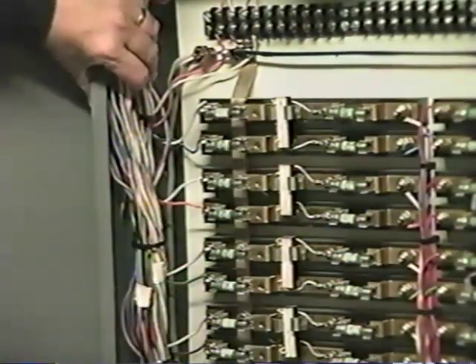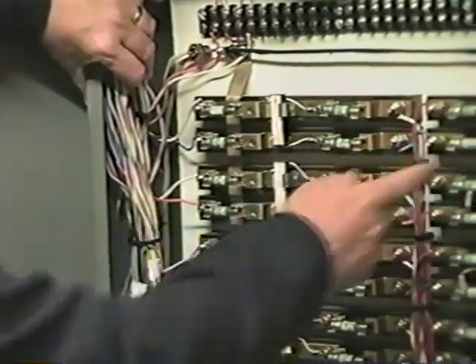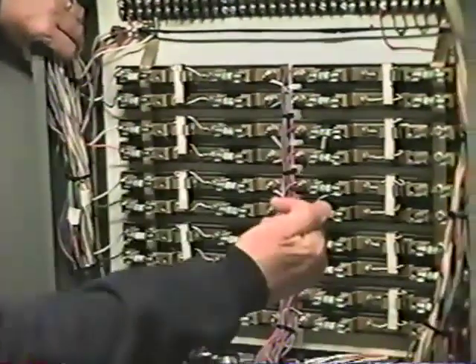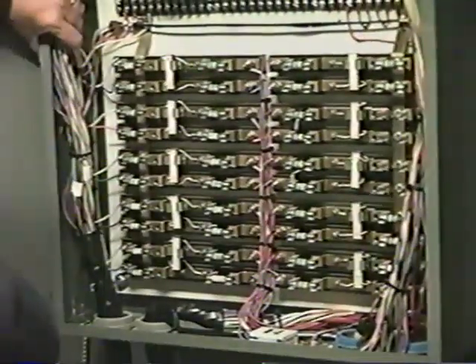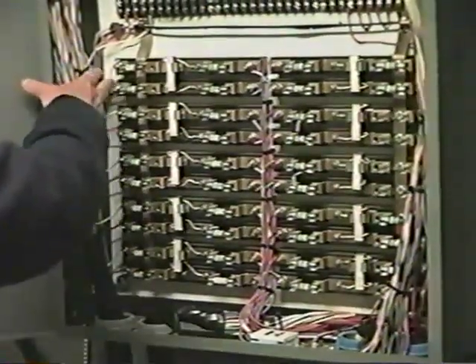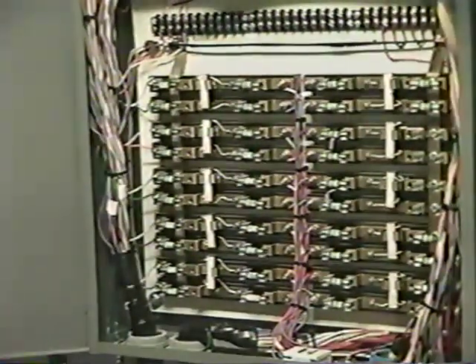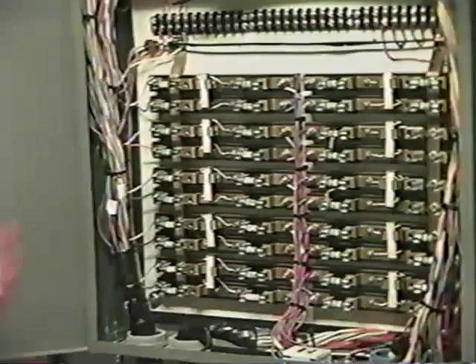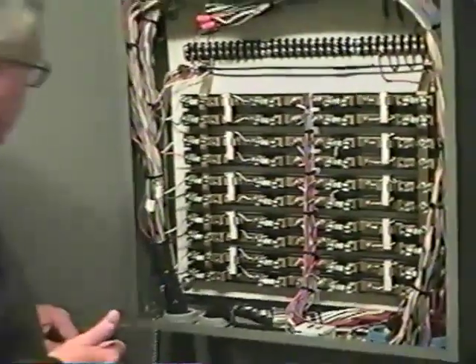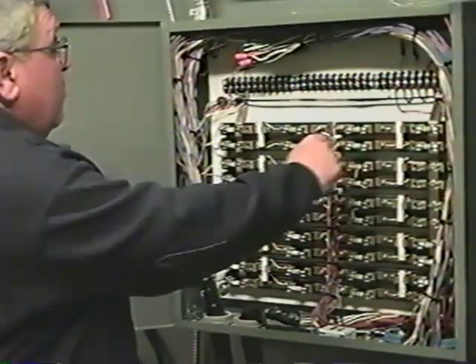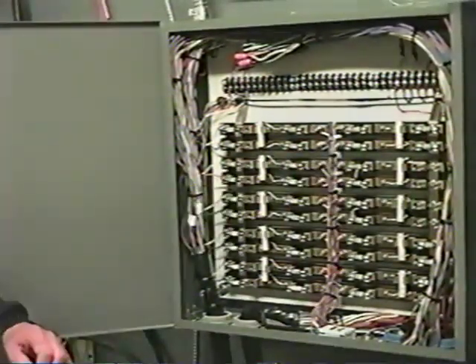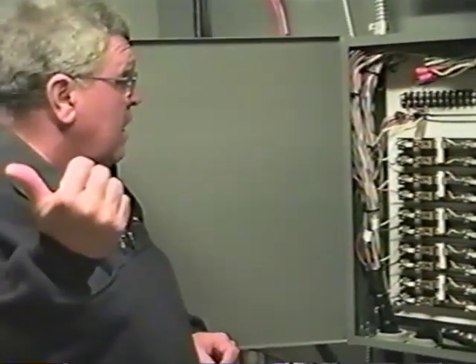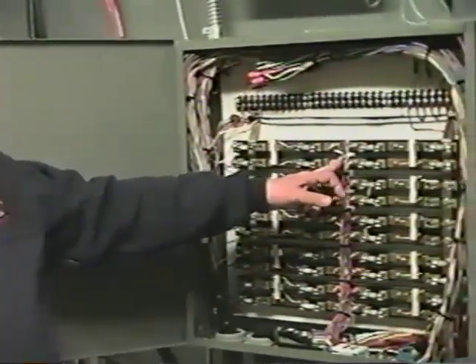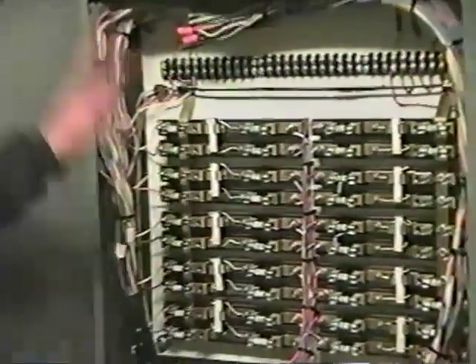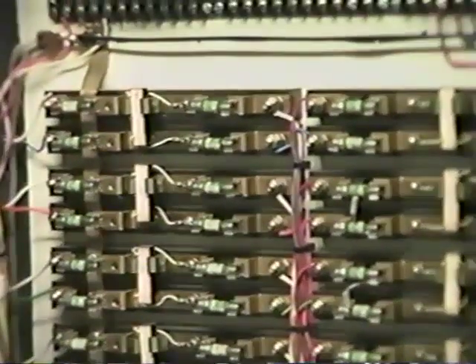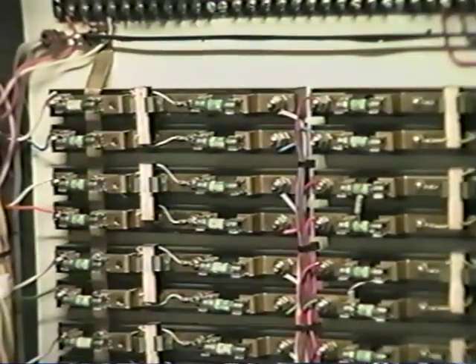So when you go into the back of the Form 4 and the Keltron, you're going to find these white and blue wires, and this goes along to Circuit 1, which we talked about earlier, that runs down to South Main Street and Eames Street. The other end of this, the white and the blue, runs out into the cabinet, and it'll follow along in that color code and that pair wherever it goes in town. We have Circuit 6, which is over here, which is a red and a blue, and you get down to the end of Ballaville Street, down by the North Intermediate School, and you're going to find a red and a blue wire. The red and the blue wire are Circuit 6, and that's all that'll ever be on the red and the blue. So that's how we keep it straight in the multi-pair cable with the wires.